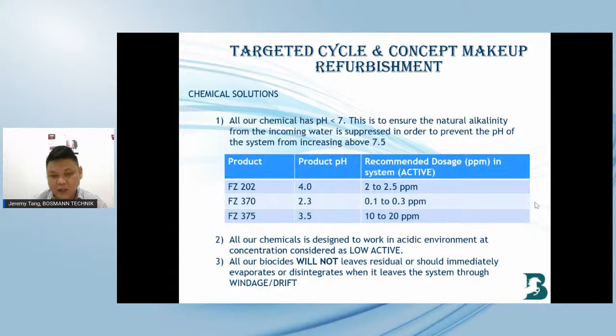For the chemical, we also need to mix it with the mechanical solution to make it fit the whole green concept of water treatment. The first one is to refurbish the makeup water using a mixed bed demineralization unit, the so-called DI. The second one is to refurbish the blowdown water before the discharge. On top of that, specialized calculation methods should be employed to trim the makeup water and chemical dosing control. Okay, we go to the next slide.